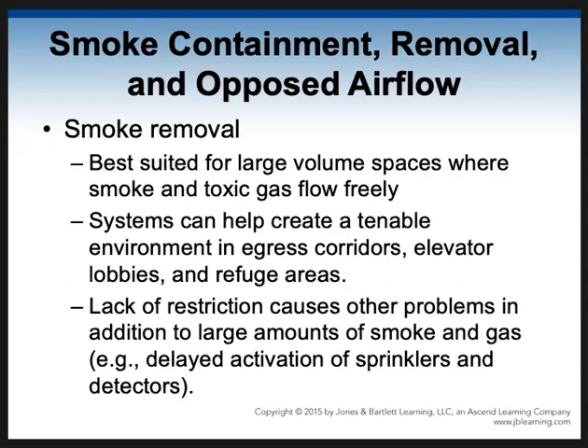Now, smoke removal, instead of that pressurization, is best suited for large volume spaces. So we're going to see big openings up on top in a mall or a big atrium where they're going to pull smoke out as fast as they can. These systems are very expensive to build, very expensive to engineer. They're best suited, again, for places like the Staples Center, or a large high-rise hotel with a big atrium or lobby. So they create tenable environments by pulling the smoke out in the lobbies and the refuge areas.